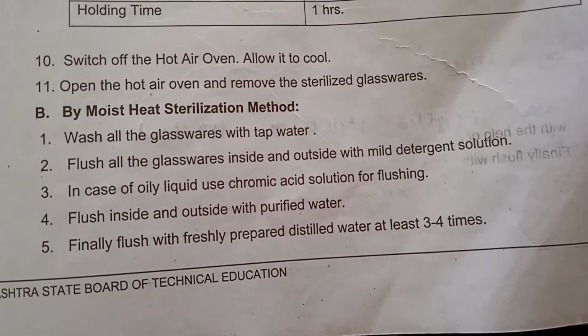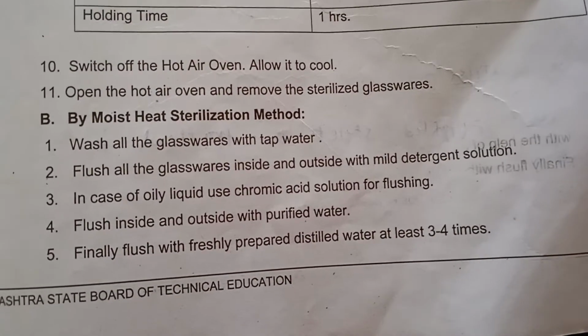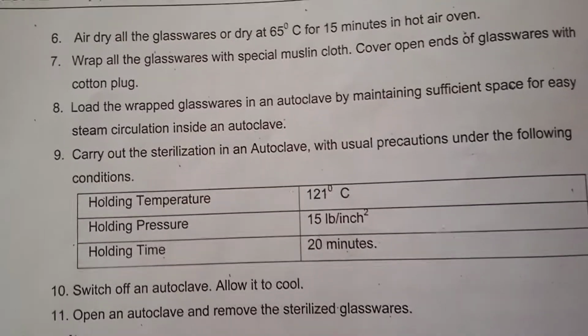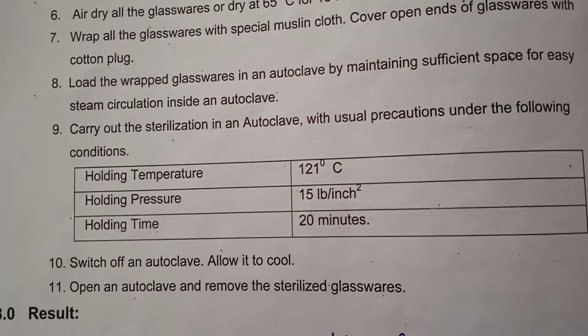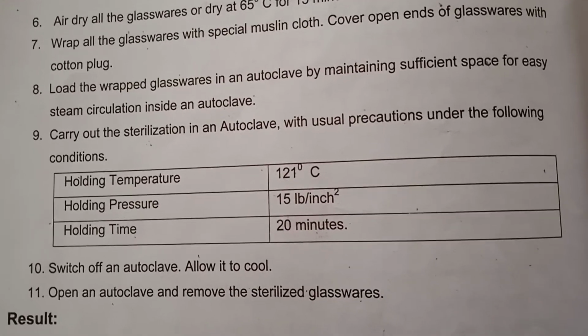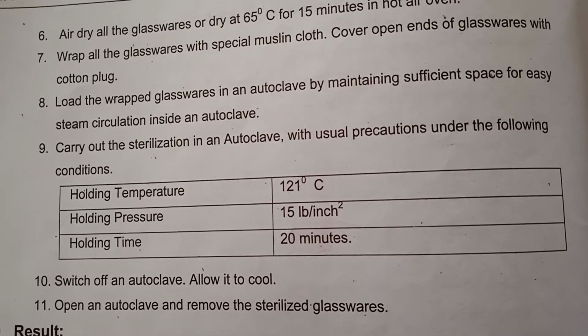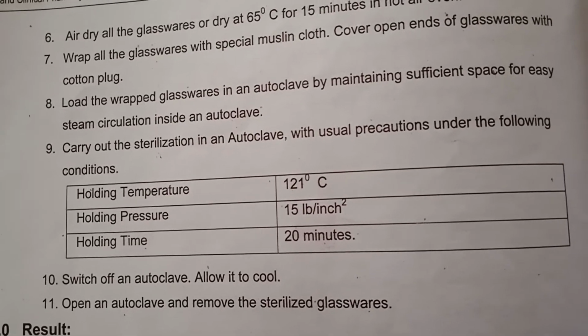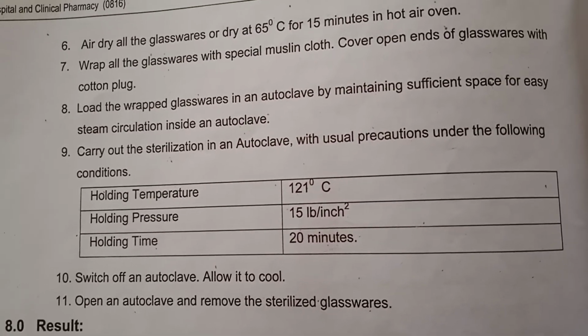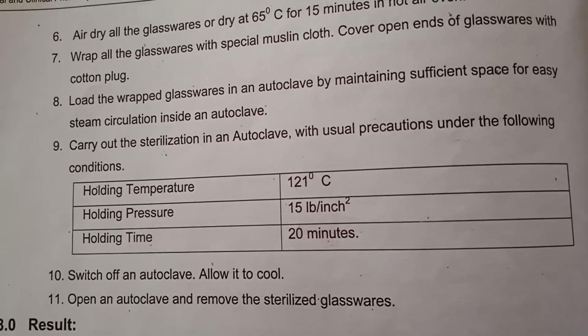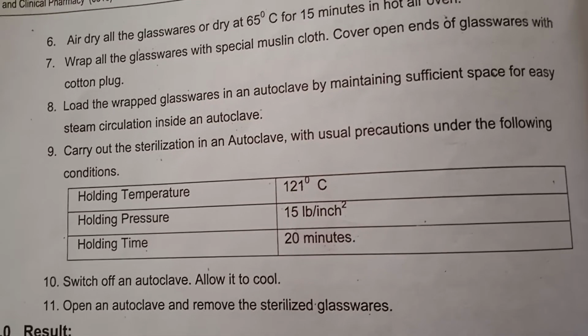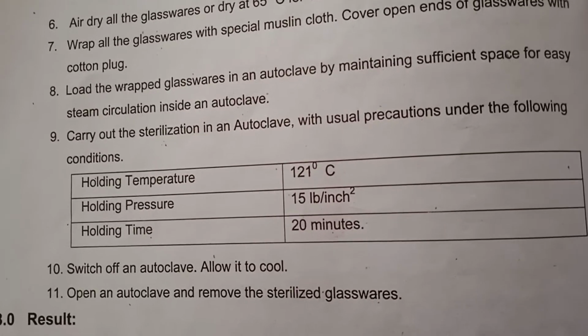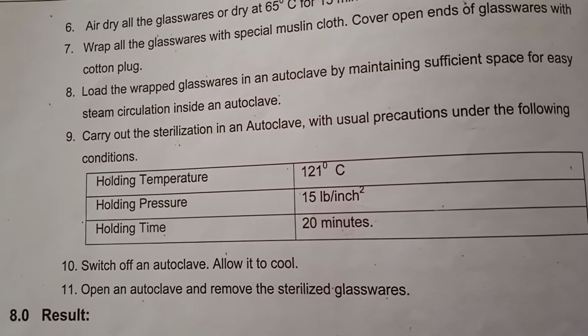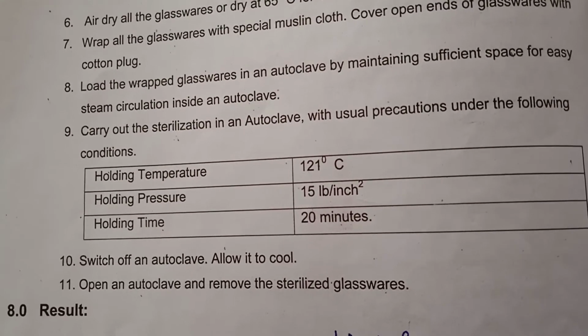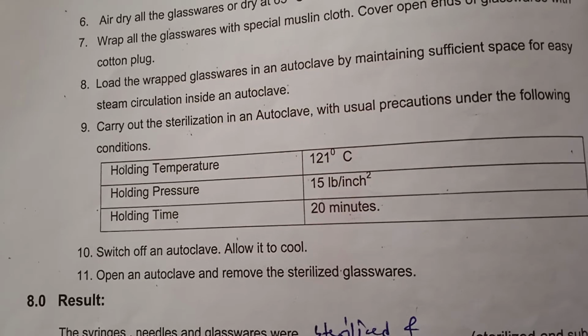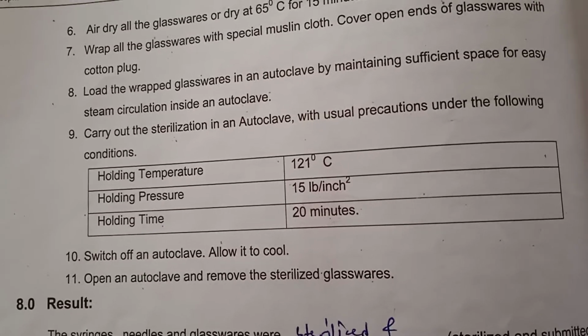The same procedure you have to follow for cleaning of these glasswares. After cleaning, we have to load it in the autoclave bin, and before loading you have to wrap it with the wrapping paper, and then keep it in the autoclave. Temperature is 121 degrees Celsius, 15 lbs per square inch, and timing is 20 minutes for the sterilization of the glassware. After sterilization, switch off the autoclave, allow it to cool, open the autoclave, remove the sterilized glasswares, and store them in the sterile area only.